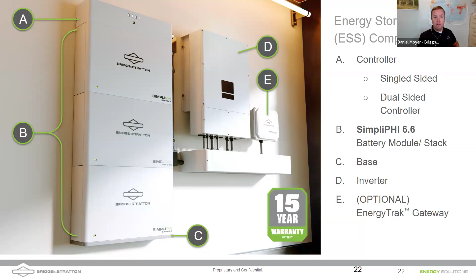Now, Andrew, we were looking at the power output of those Sol-Arks, right? The 18K can do 18,000 watts from batteries to loads. Your 15K can do 12,000 watts from batteries to loads. That new 12K coming out is 10,000 watts from batteries to loads. What I'm showing on the screen is you can have a single, double, or triple stack of our batteries, but I want to call out the continuous power output of the battery stacks. So if we've got this 3 stack right here, that's 14,000 watts continuous output. That's perfect for a Sol-Ark 15K — you're only asking for 12 from the battery, and the battery can do 14. The bottleneck is not in the battery.